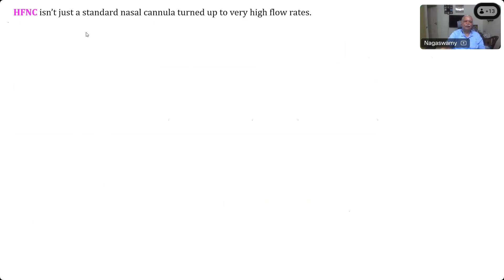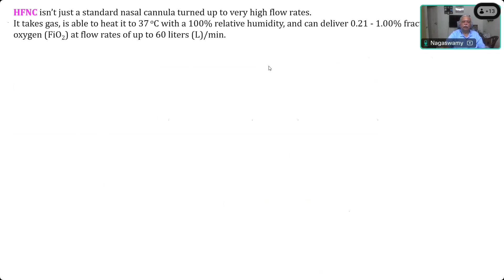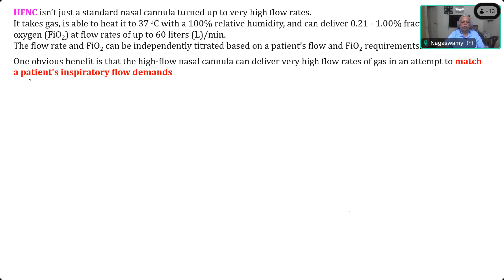So it takes gas, heats it to 37 degrees with 100% humidity, and can deliver a fraction of inspired oxygen from 0.21 to 1 with flow rates up to 60 liters per minute. So that is why it is called high flow nasal oxygen. Flow rate and FiO2 can be independently titrated to the patient's flow and FiO2 requirement. And the main obvious benefit of high flow nasal cannula is that it can deliver very high flow rates of gas to match or exceed patients' inspiratory flow demands.